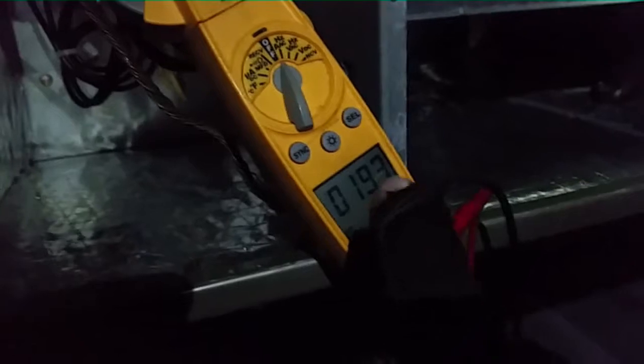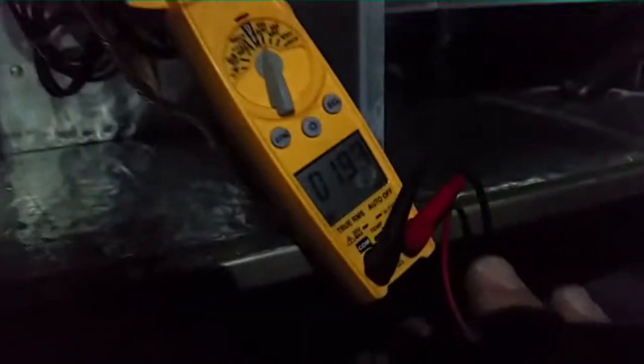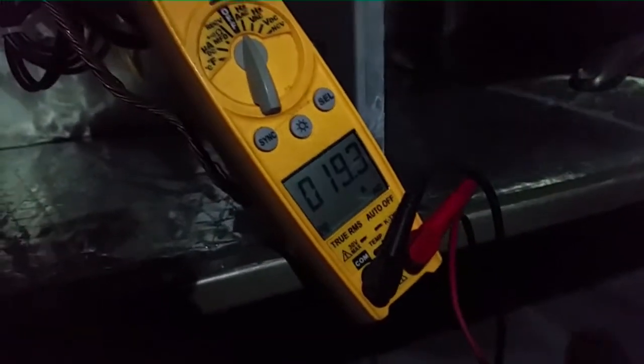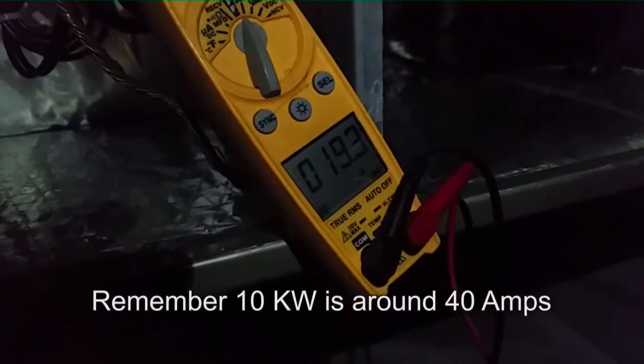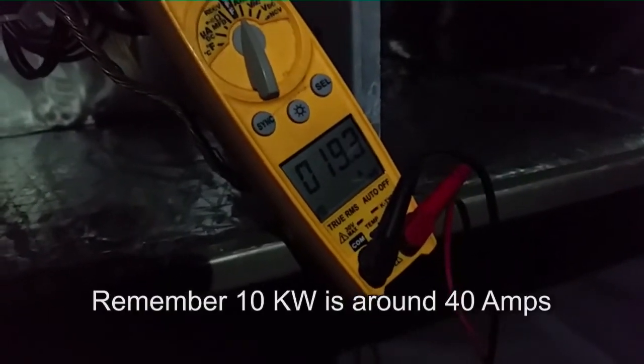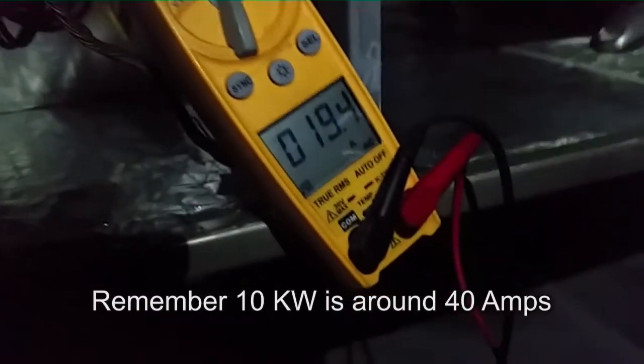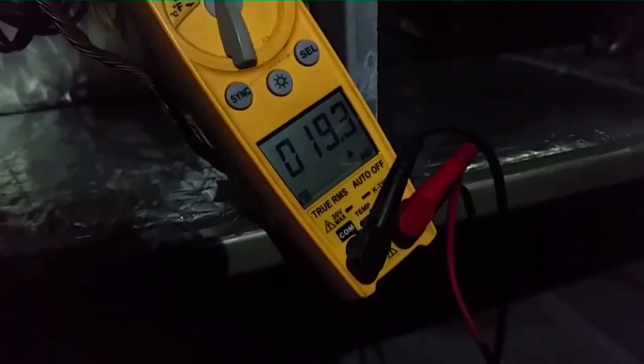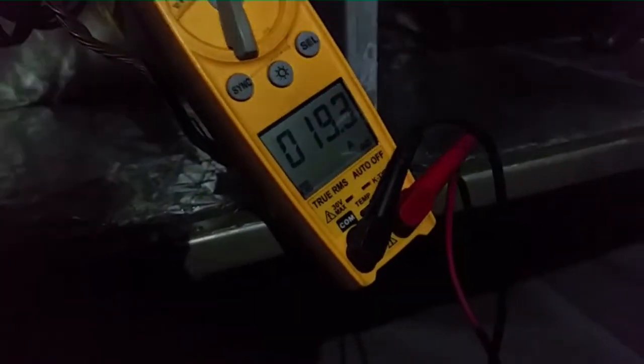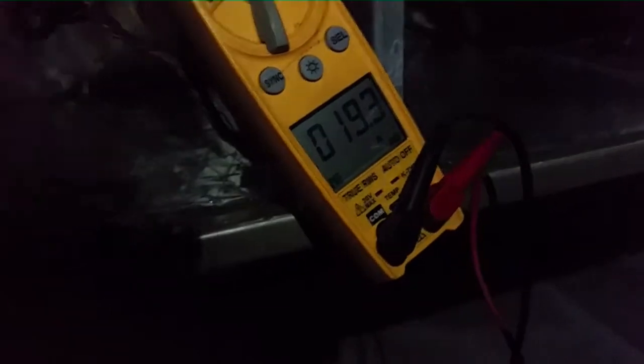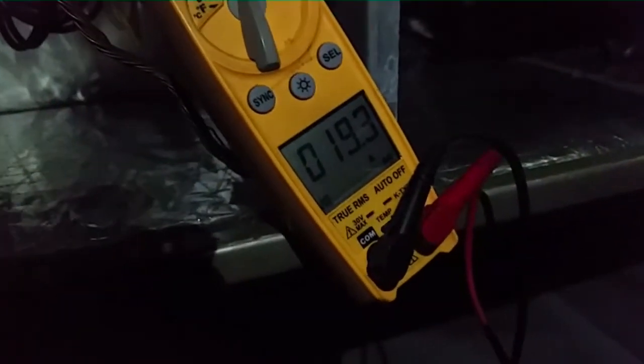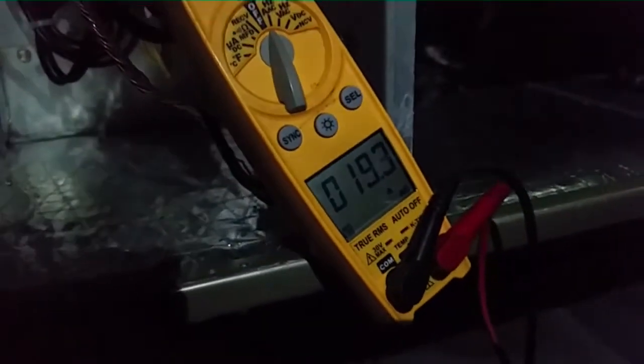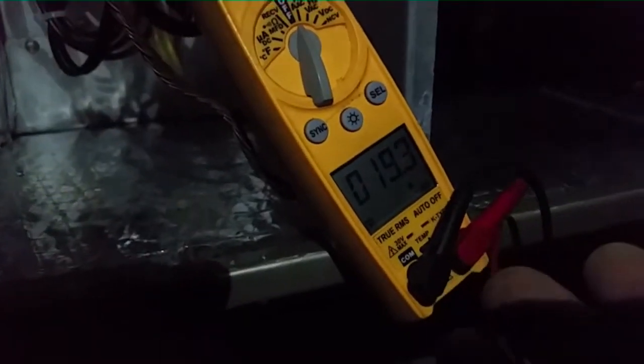We see 19.3 amps. Now this is a 4-ton system with 10 kW on it. On 4 tons you typically use 10 or 15. In some other locations of the country which are a little bit colder than this, you might actually use 15. But for here, I found that 10 works pretty good for me, and it overcomes defrost just fine. Haven't had any issues with that sort of thing. That's sort of a different debate. So we know there's only one bank of the heat strips on.